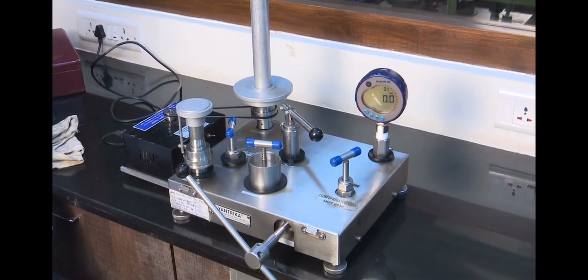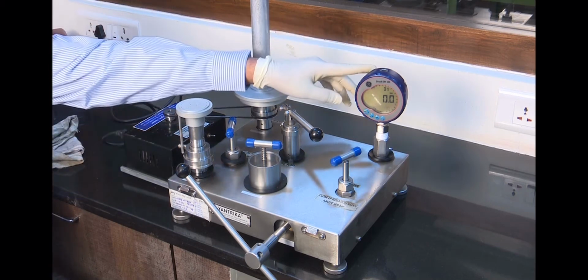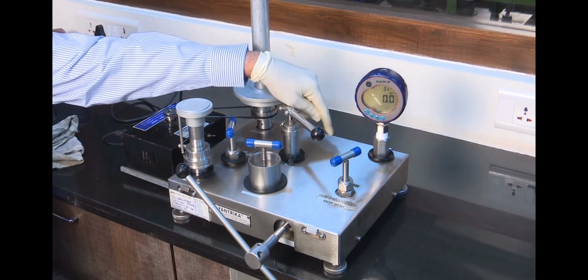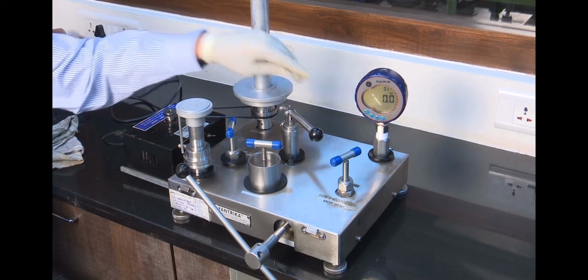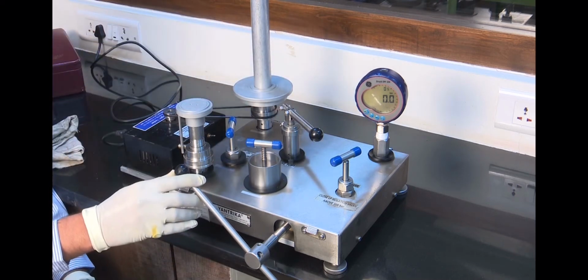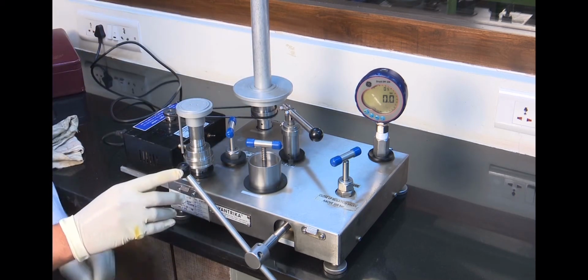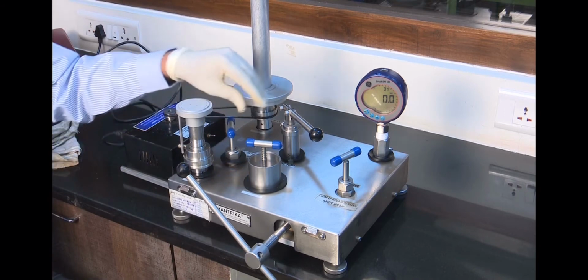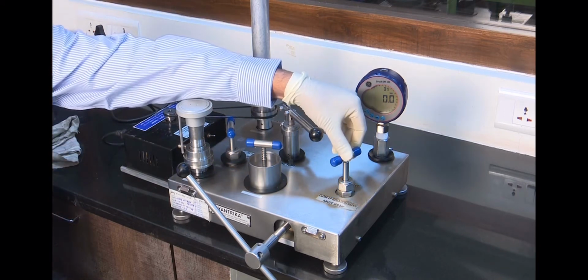For calibration, we need to do some preparation. For this, I have already mounted pressure gauge UUC on dead weight tester. Turn the screw pump handle clockwise fully. Open the HP valve and close LP valve.